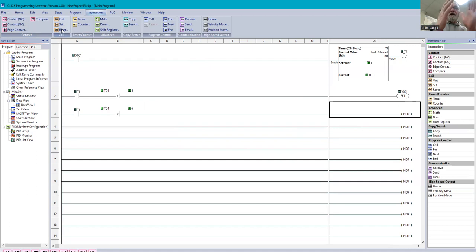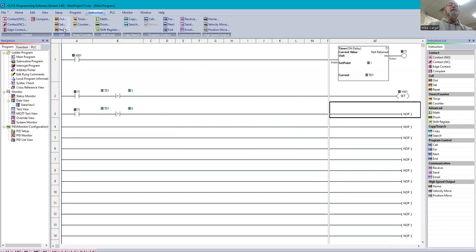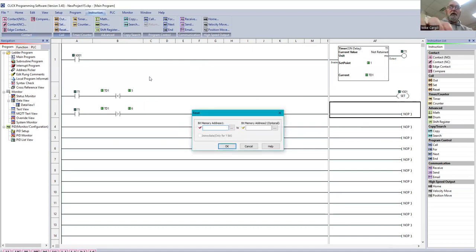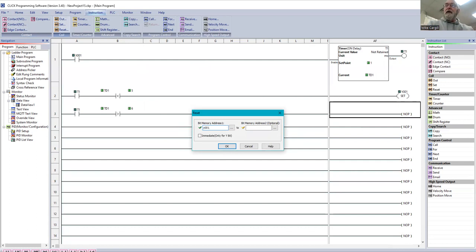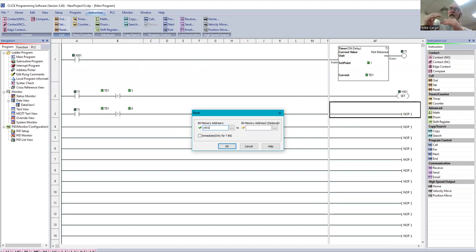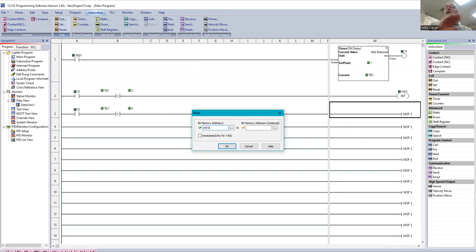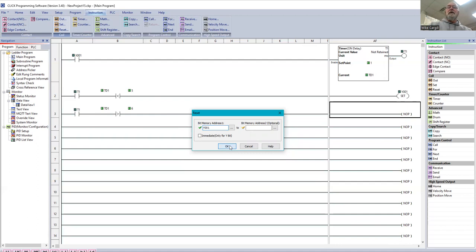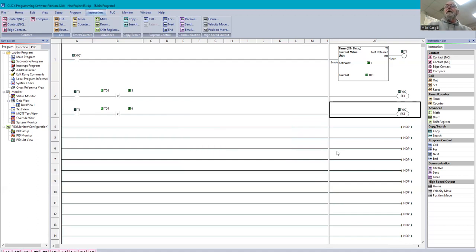If you have a set, you have to have a reset. So now we're going to turn it off with a reset, and we're going to turn off Y001. Now, this allows me to give it a second address. If I just use an out, when I turn it off on a second address, I've already said don't turn on, never turn on. But with a reset, I can turn it on and turn it off.